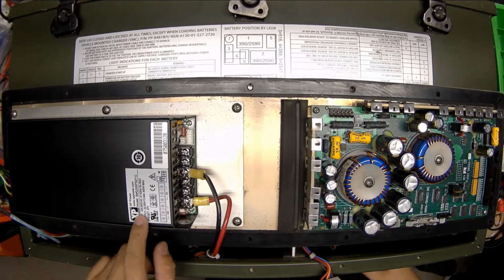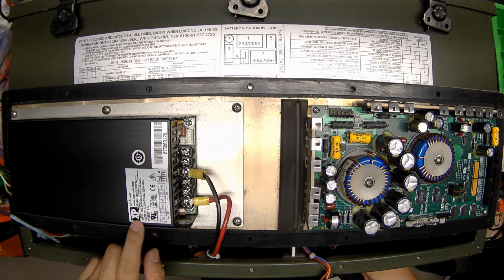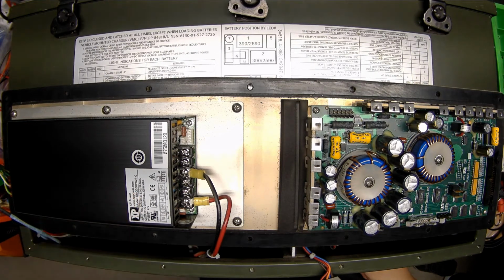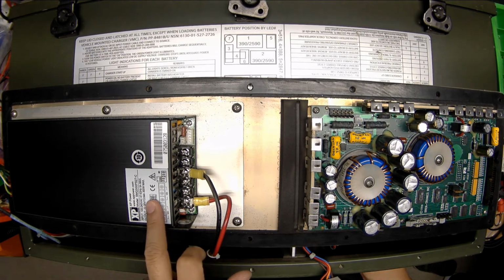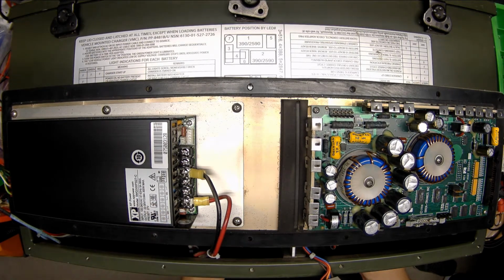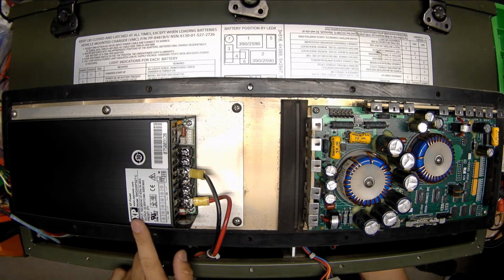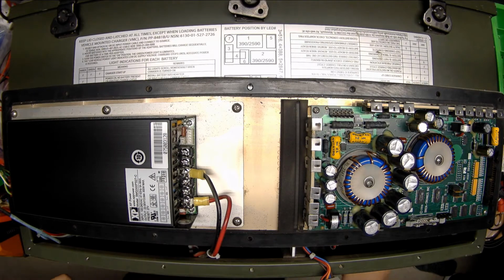We have a universal power supply, 110 to 240 AC, 47 to 63 hertz, 5 amp max, output 22 to 30 volts at 13 amps, 300 watts. Preset to 27 volts. We'll have to see if it's actually that voltage.